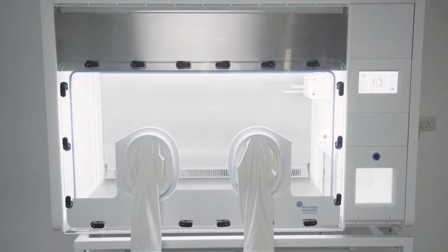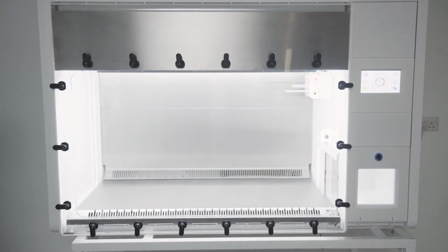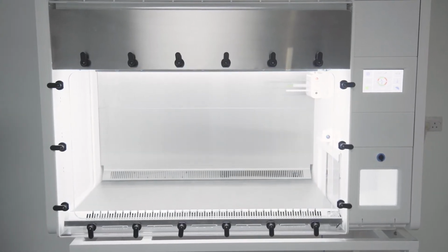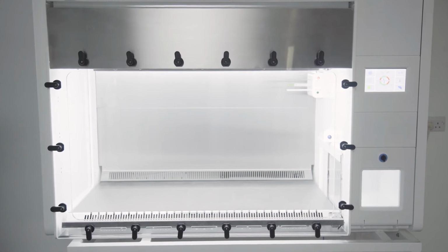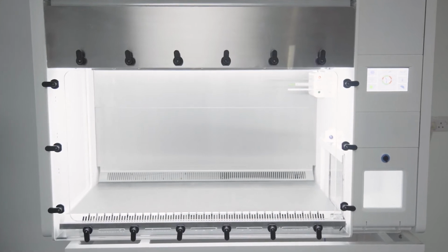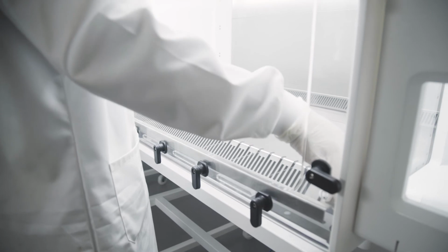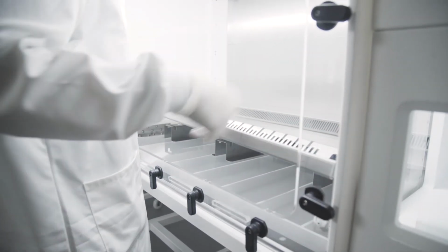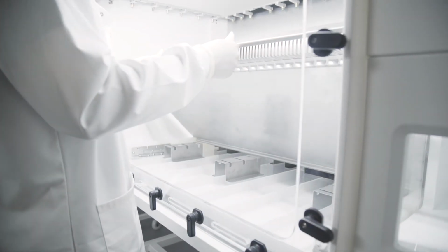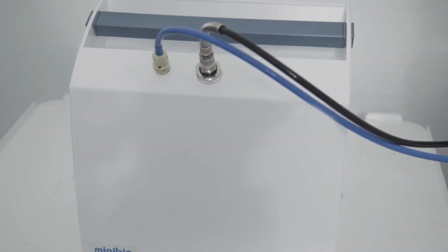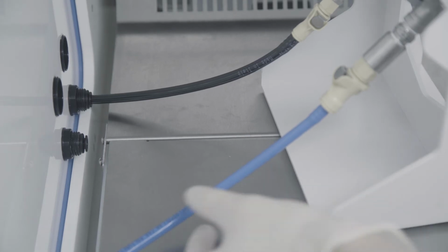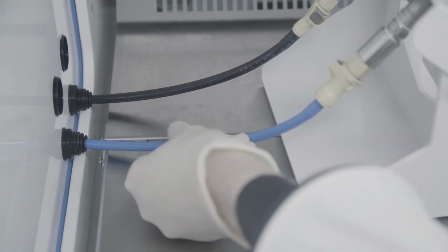The workstation is fitted with a removable front as standard to facilitate the movement of larger items into the workstation and allow access for thorough cleaning. The stainless steel floor can be easily repositioned to allow cleaning of the underfloor area. Hydrogen peroxide fogging can be used to decontaminate the Whitley A135 GMP workstation.